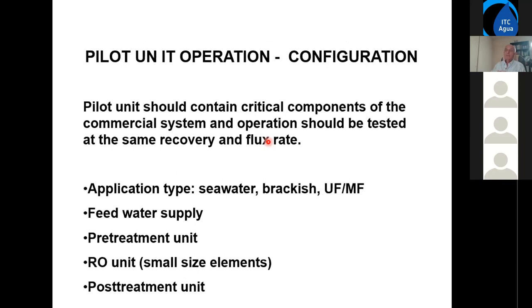Okay, so if we want to do a full-fledged pilot unit which mimics the operation of the commercial plant, it's prohibitively expensive. It's so expensive that usually there is no money in the project for this. But we can test critical components. For example, we can test part of the pretreatment, media filtration. We can test the operation of the pretreatment and the lead element, okay? Maybe with recirculation, we can take the operation of the pretreatment and simulate the operation of the last element. So everything has to be done in a smart way, because usually we do not need a full-fledged pilot unit to mimic the complete plant. We need the critical components which we're not sure about.